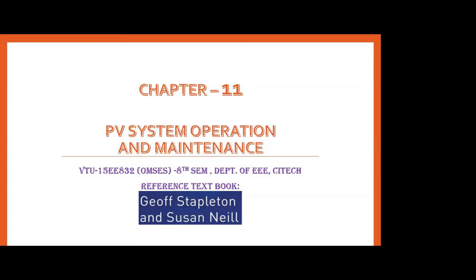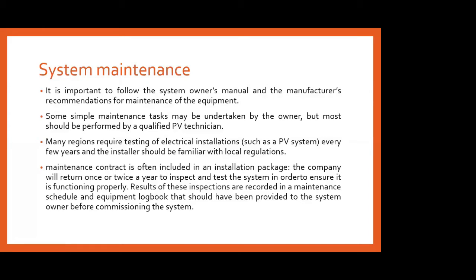Once the commissioning has been done, the next important part which we have to take care of is the PV system operation and maintenance. What do we mean by PV system operation and maintenance? Of course, it is important to follow the system owner's manual and the manufacturer's recommendations for the maintenance of the equipment, because each of the components we are using will be in use for a minimum of 15 to 20 years.